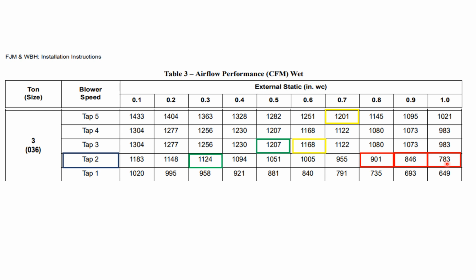Now, imagine you putting a 3-ton system in, and that unit's only putting out 783. You're not even putting out 2 tons of air. Now you can understand why a compressor would blow up, lock up, open windings, go off on a high head, making all kinds of rattling noise, because pressure has to go somewhere.